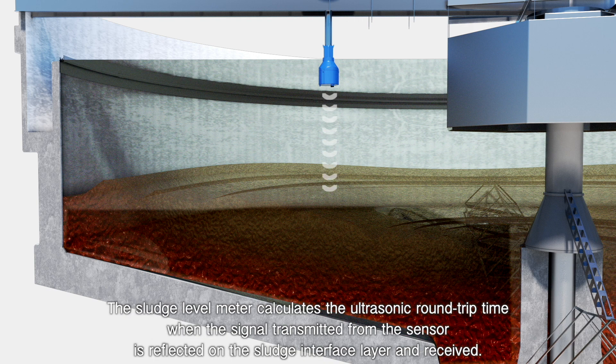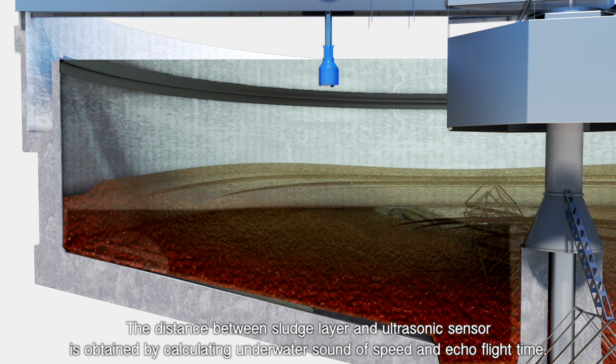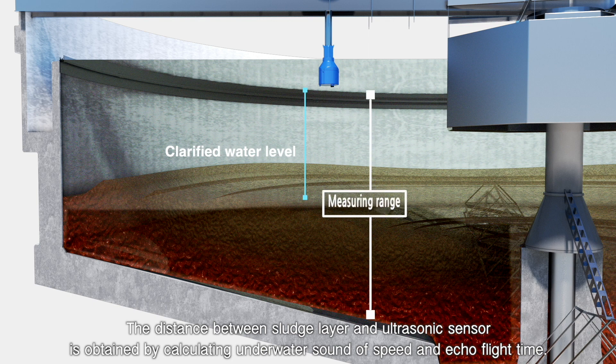The sludge level meter calculates the ultrasonic round-trip time when the signal transmitted from the sensor is reflected on the sludge interface layer and received. The distance between sludge layer and ultrasonic sensor is obtained by calculating underwater sound of speed and echo flight time.